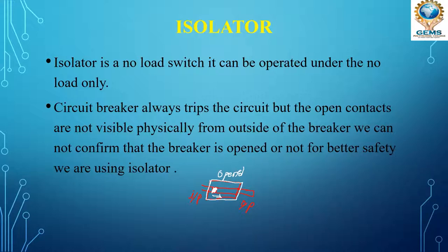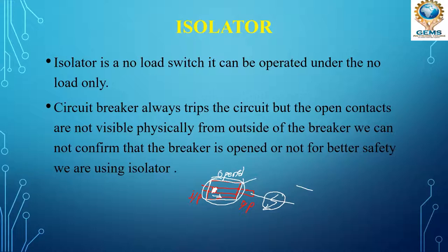But we don't know whether the circuit is opened or not, because it is enclosed in a chamber — it is closed in a box and not visible. If we want to repair or work on this line, we cannot do so with confidence because the contact position is not visible. This is the reason we keep in series one more device: the isolator.